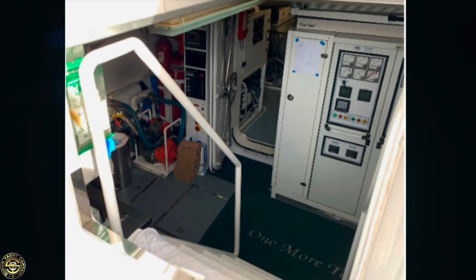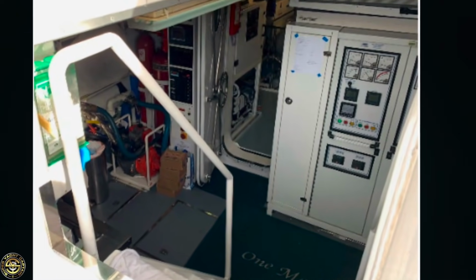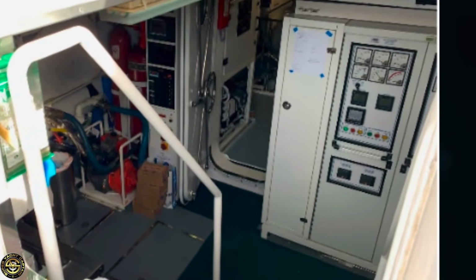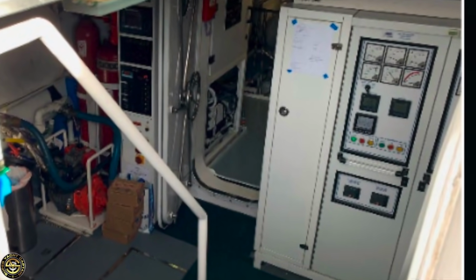The yacht's electrical generation and earthing system. Now, they're obviously going into this because the engineer lost his life due to electric shock. One More Toy generates three-phase electricity at 480 volts and 60 hertz. This allows electricity to be distributed at either three-phase 480 volts or single-phase 277 volts AC. Other voltages are supplied on board the yacht via step-down transformers.